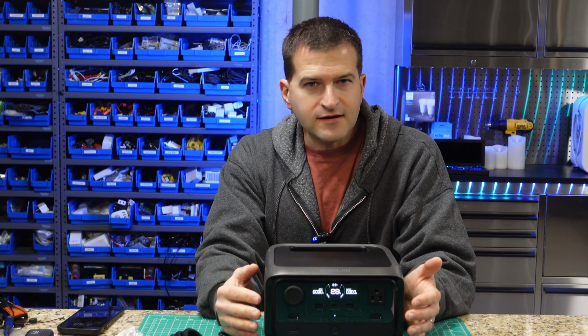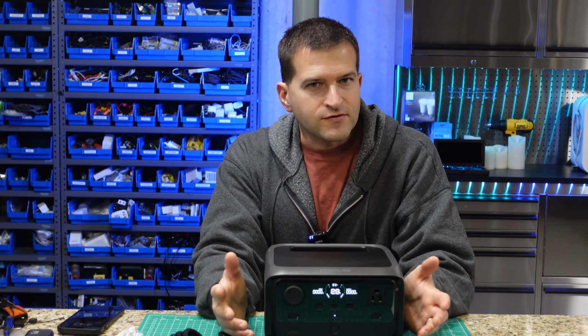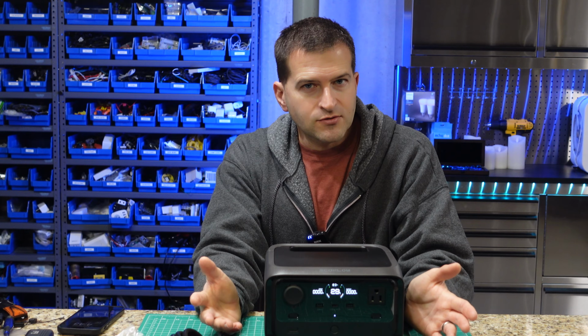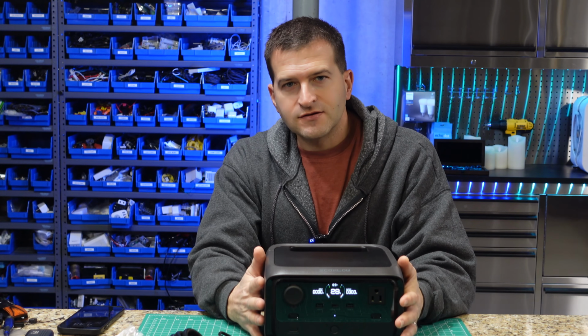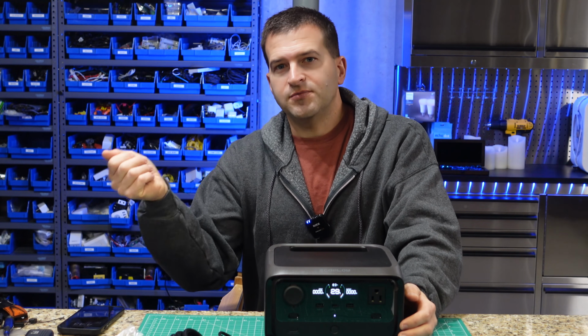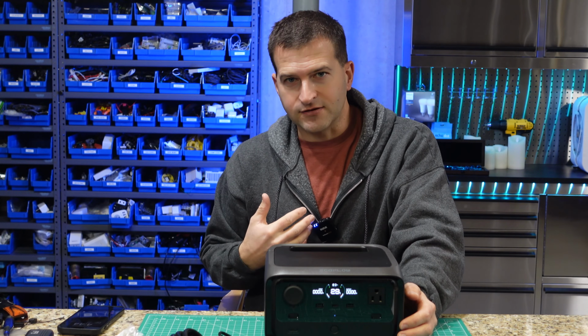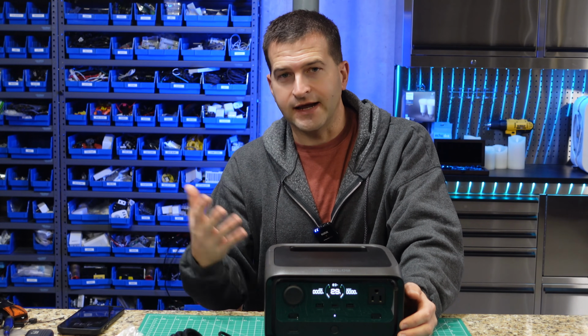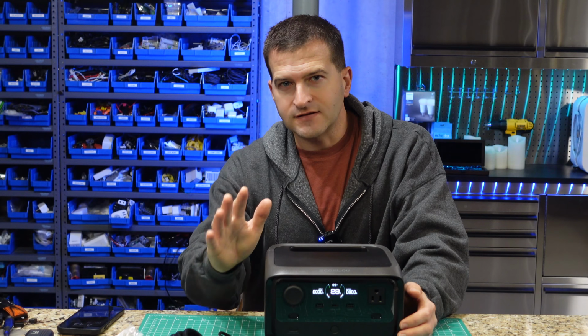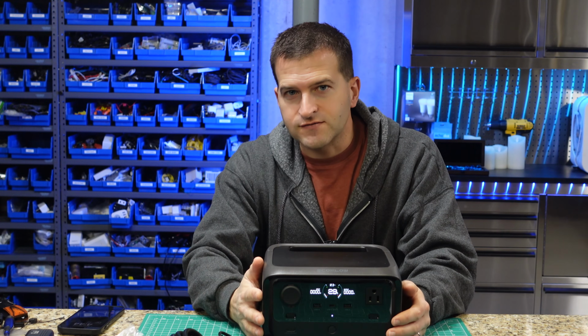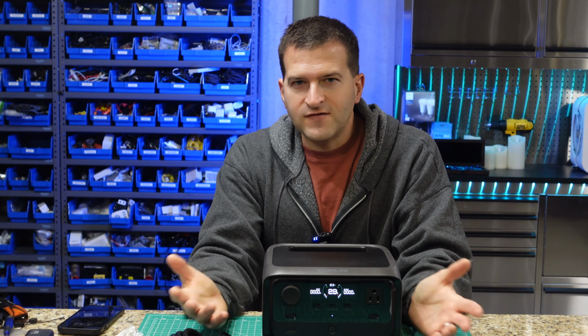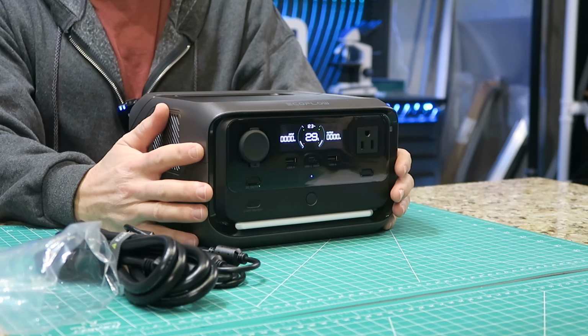It adds a lot of cost doing that, and maybe it's not worth it for everybody, but I always put a PDU in the rack, because if you have to do maintenance on your UPS unit, you can plug the other side of the PDU into the wall while you're pulling out your UPS unit, without taking everybody offline. So if you already have a rack with a PDU, that's a very viable solution if you plan on using this for a rack. Not so viable for a desk situation.